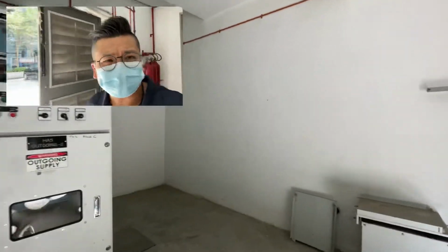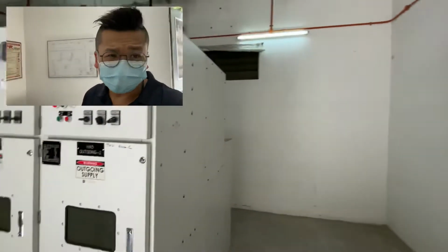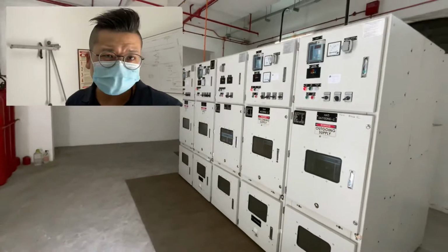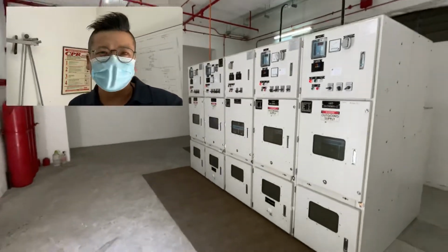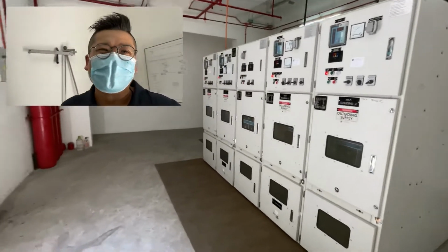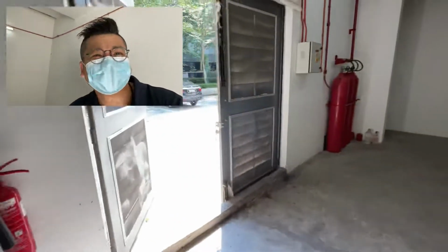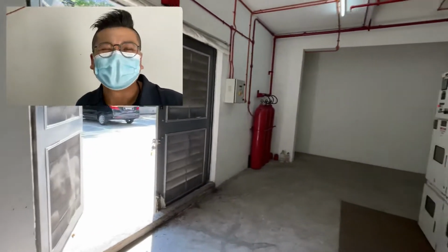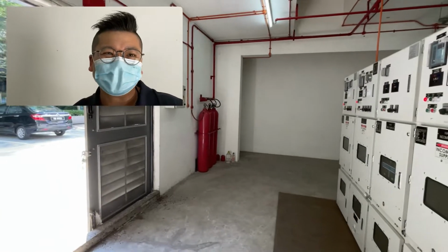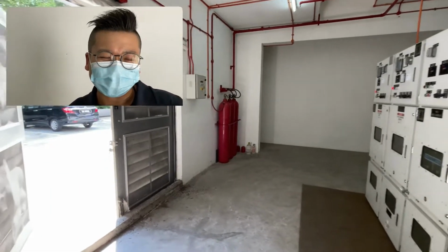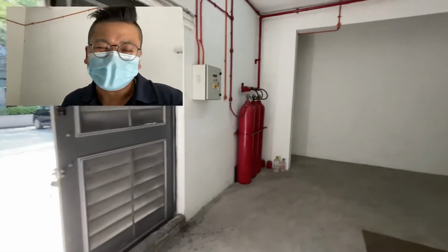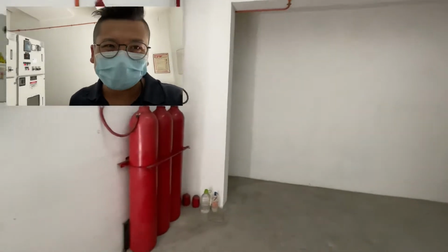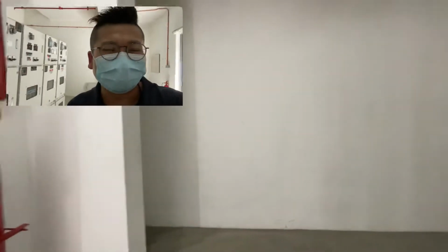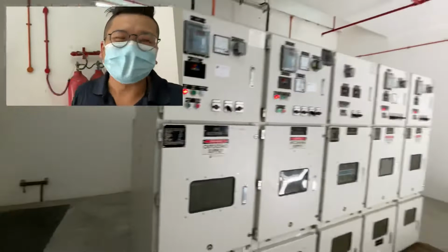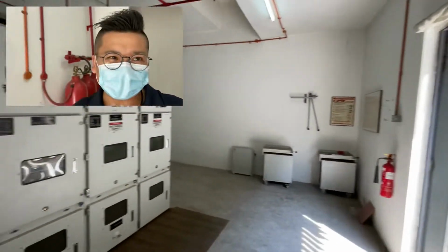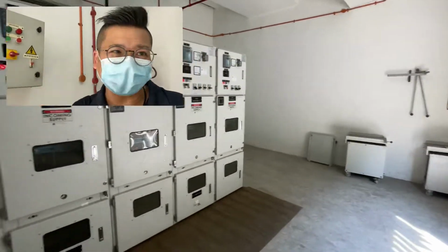After genset test run, currently I'm inside the HV room. This is the main HV room for the condo. It is recommended not to run your genset without load for more than 10 minutes. If you run more than 10 minutes, there will be a lot of unburned fuel kept inside the combustion chamber, and eventually it will leak out from the exhaust gap or clearance.